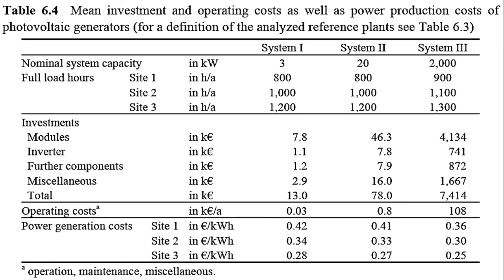advantages are partially compensated. The major share of expenditures accounts for the module cost. For monocrystalline, for example, modules which have a monocrystalline solar panel included in them, the expenditures are roughly between 2000 to 3000 euros per kilowatt. The prices for multicrystalline photovoltaic modules are slightly below this order of magnitude. They vary around 1900 to 3000 euros per kilowatt. According to this, the cost for the modules contribute to about 55 to 60% of the overall investment required for the entire photovoltaic generator. We have also done a comparative analysis of different types of modules. We have seen that their efficiency also varies. So choosing a right type of solar panel module can be a little tricky.